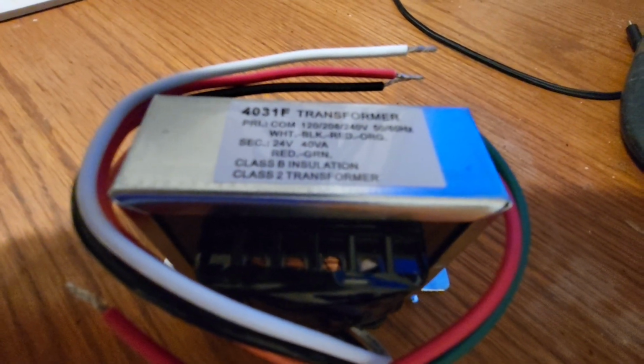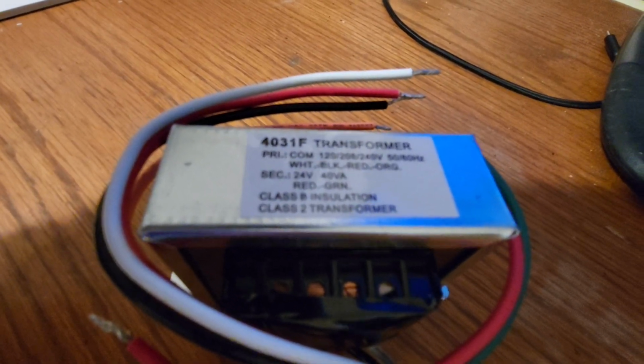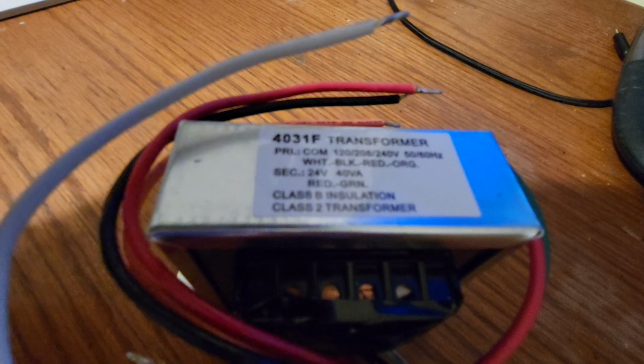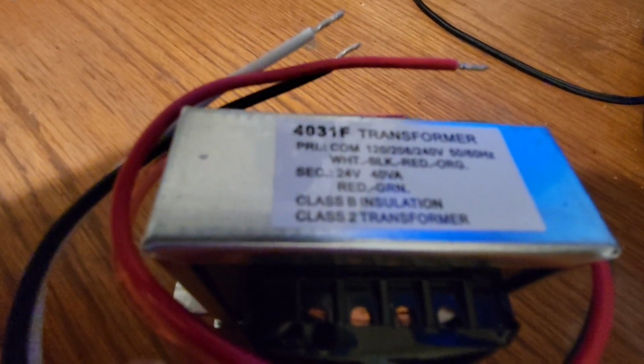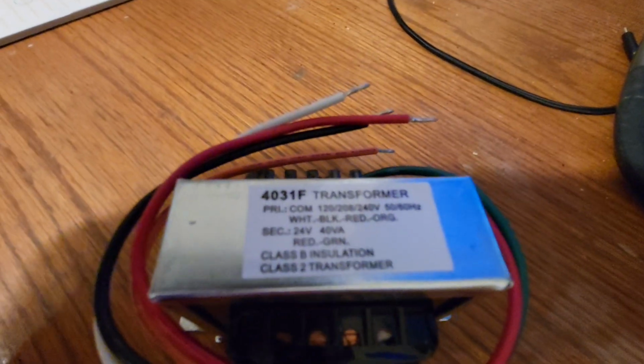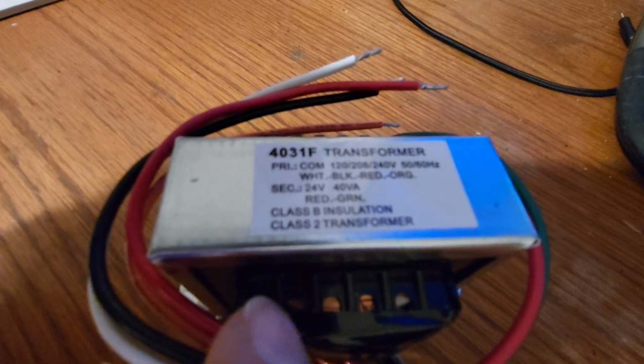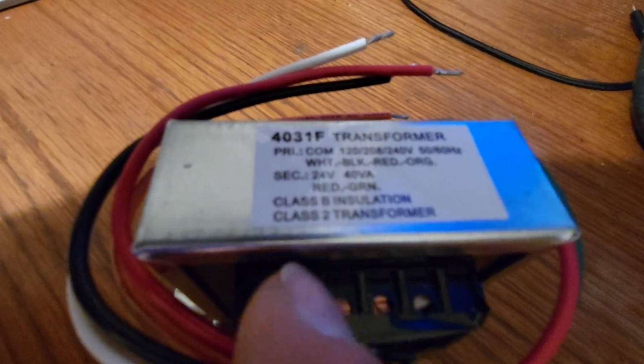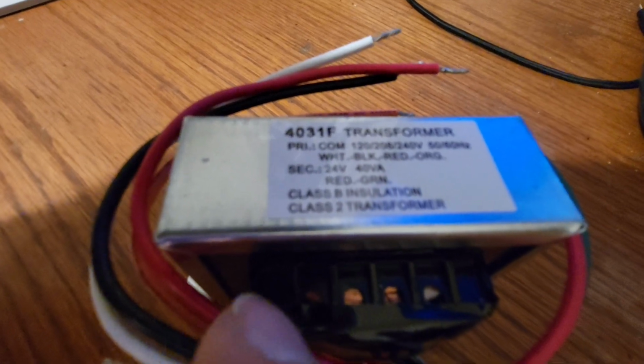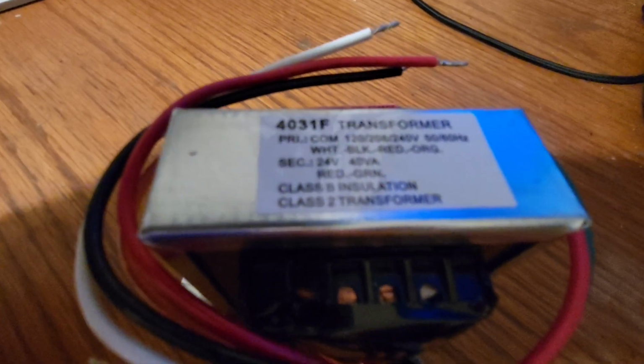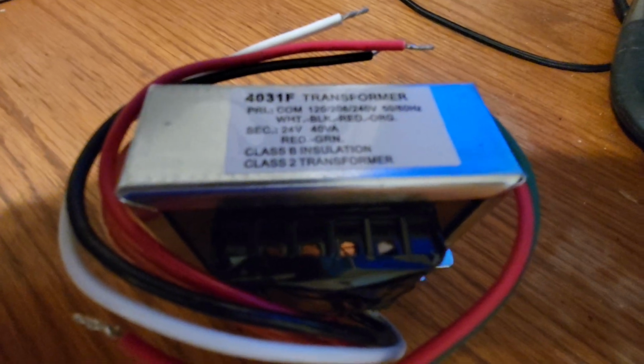The other way you can do it is not isolated, so it's not as safe, but you can also use this as an autotransformer, like a variac. So you take the white neutral on the primary and hook that to your load. In this case, the black is 120. Hook that to your 120, and then the orange is 240. You'd hook that to your 240 load. Basically you hook 120 in between the neutral and the black, and then the rest of that winding turns into an autotransformer and boosts that voltage up to 240 output, and you get 240 out of this thing.